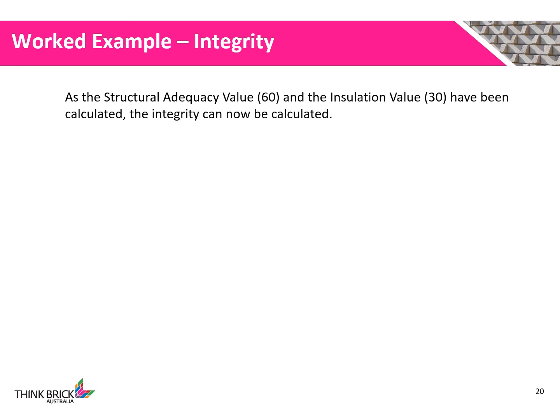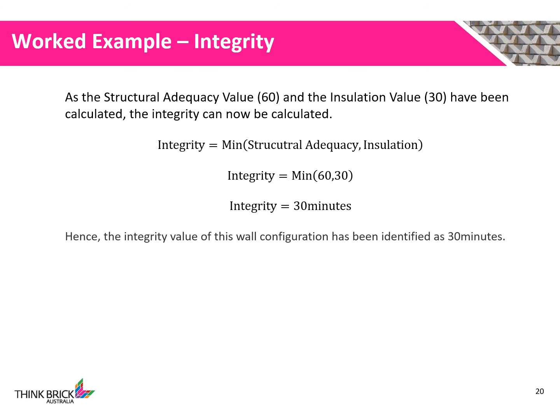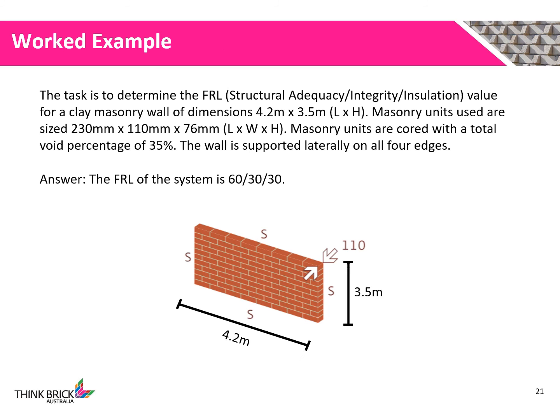Determining the integrity value is now a simple task, as we know the structural adequacy and insulation values. Selecting the minimum of the two values, we determine our wall's integrity value to be 30 minutes. With that, we've evaluated the FRL design for our masonry wall. It would be presented as a 60-30-30 wall, as annotated by the NCC.